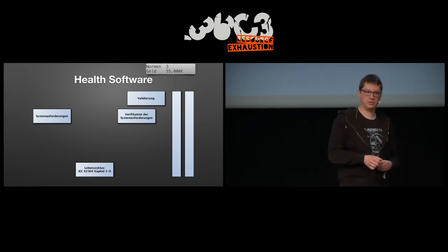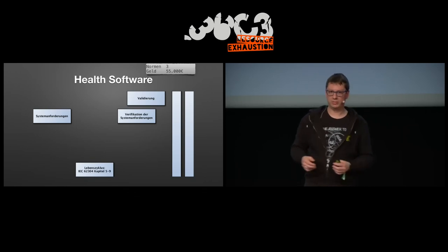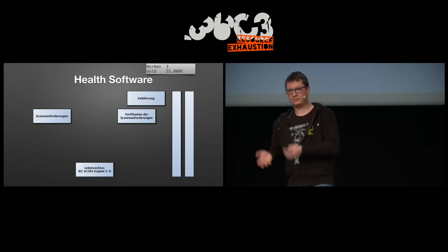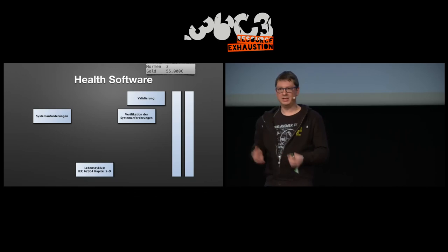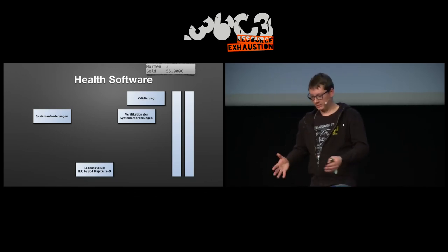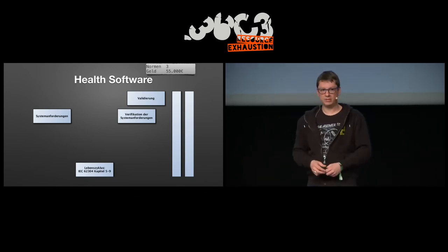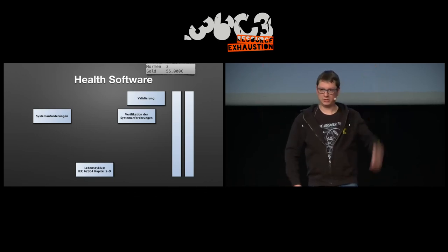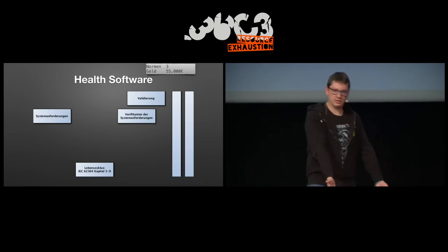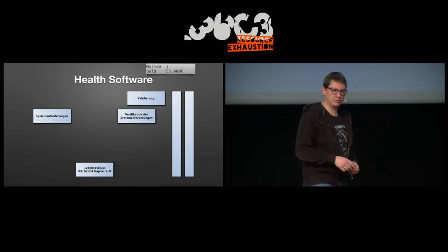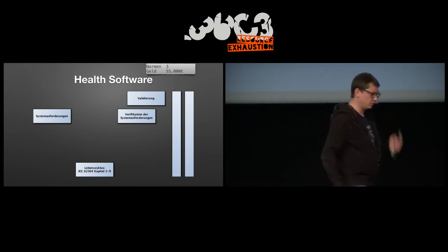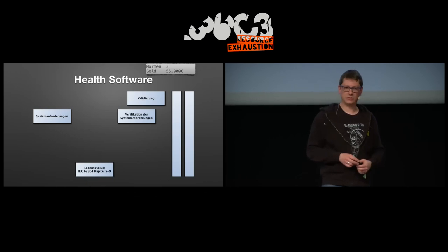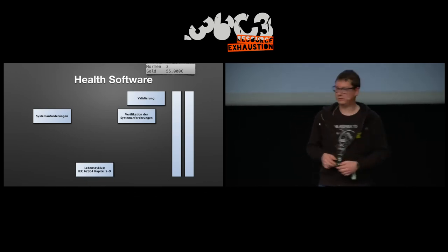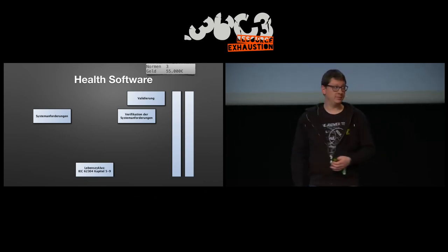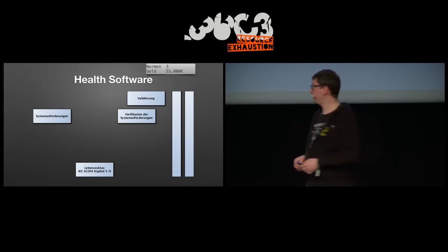defined that specified users, specified product, in the specified environment, people can use this product. So you can verify the product, but people can't work with it because, for example, if it's too dark and people can't see anything, that's where the standard on validation comes on top of the verification.